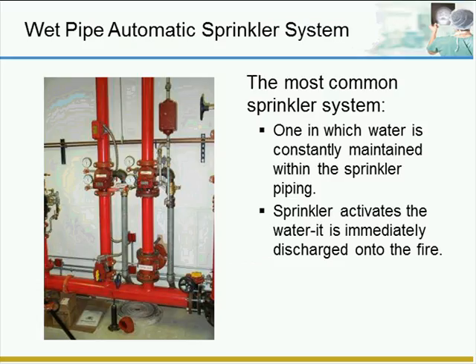This is a photo of a wet pipe sprinkler system. The larger pipe on the bottom is a 6-inch, which comes from the underground from the street, which we spoke of. And then you have two separate wet pipe risers. Those are the 4-inch lines perpendicular to the 6-inch main. About halfway up these 4-inch lines, you'll see two sprinkler alarm valves. This is where the dials and gauges are. When the system activates, a flapper within those alarm valves will open, sending the central station alarm to the fire department or alarm company so that they can respond.